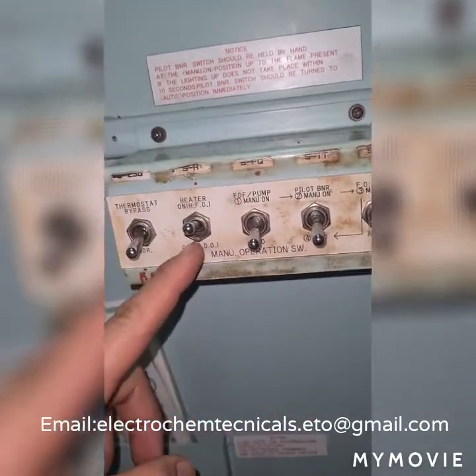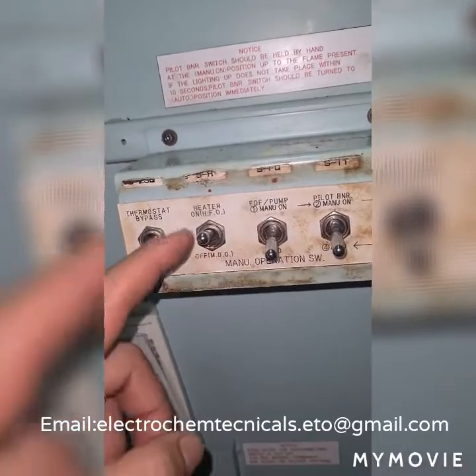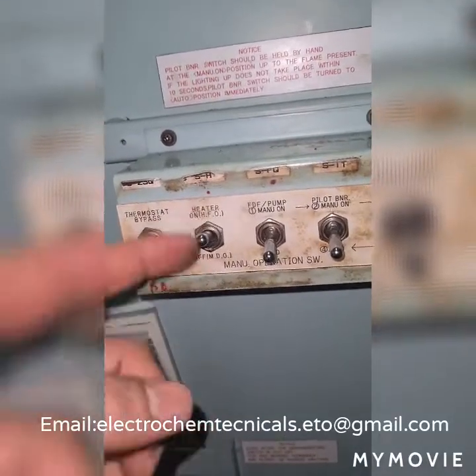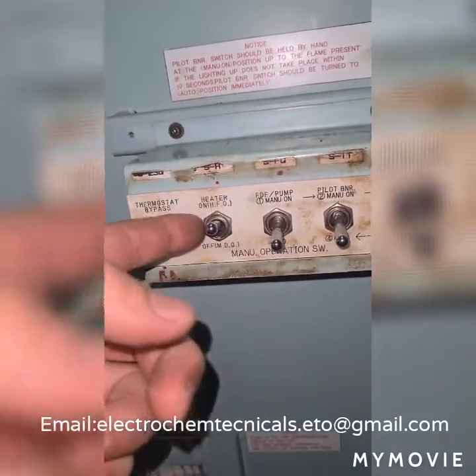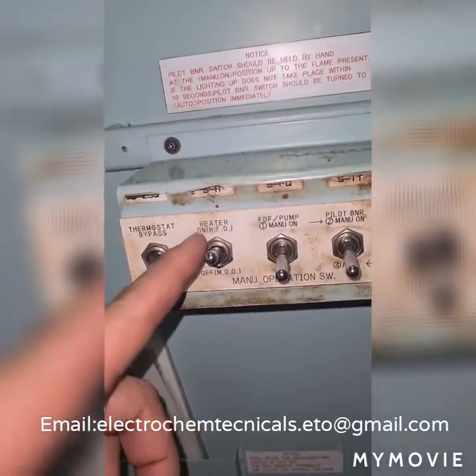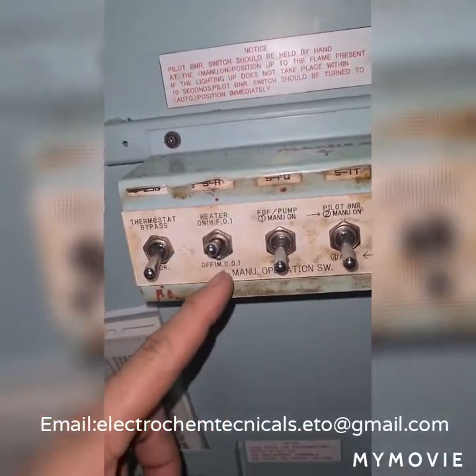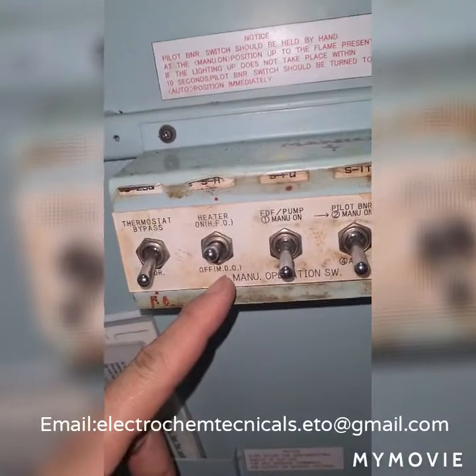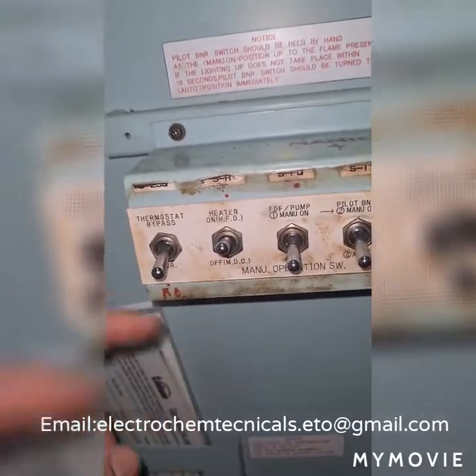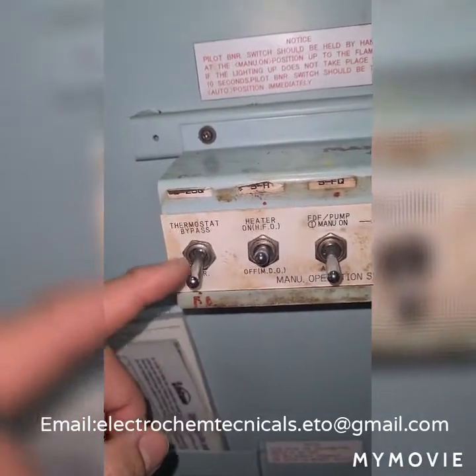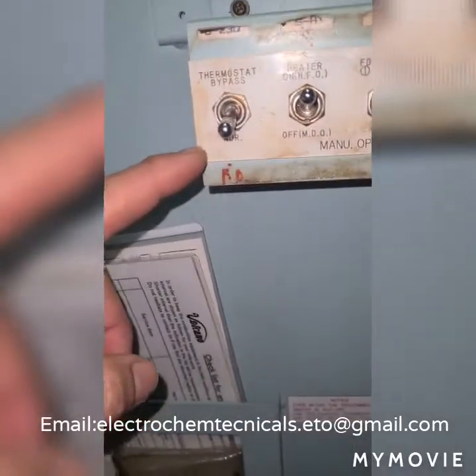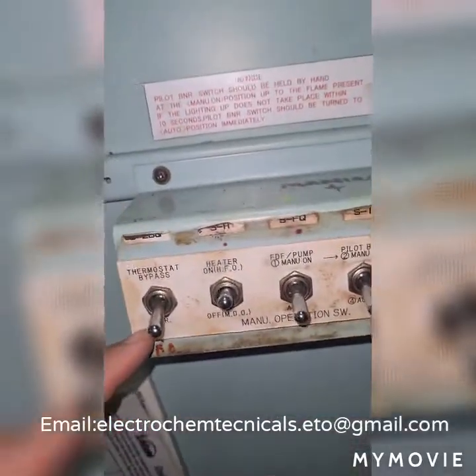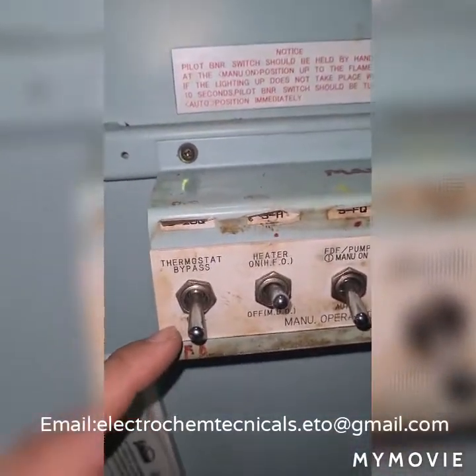This is the heater. It is for heavy fuel oil. If you put it up, it means you are going to use the heater for heavy fuel oil. If you put it down, you are using diesel oil without the heater. And this is the thermostat bypass. Normally, it is put in the low position.